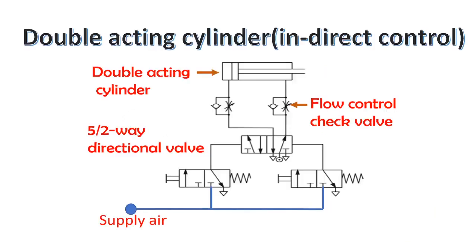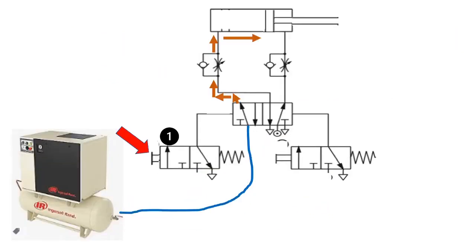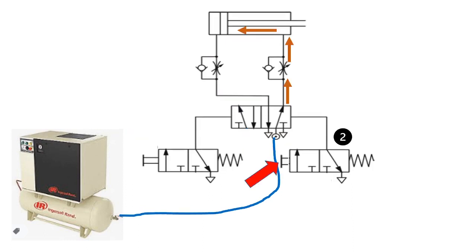This is a double acting cylinder with indirect control. A double acting cylinder is to advance when push button number one is pressed and will remain extended until push button number two is pressed. When push button number two is pressed, the cylinder is to retract.